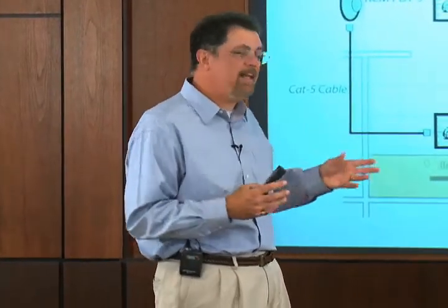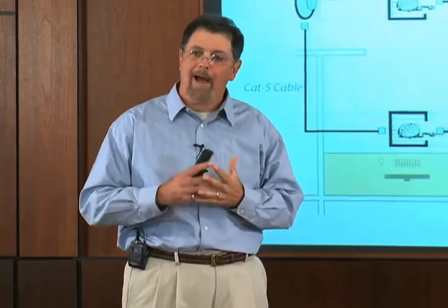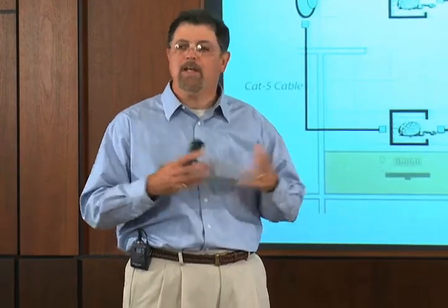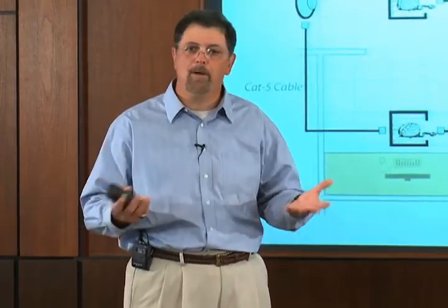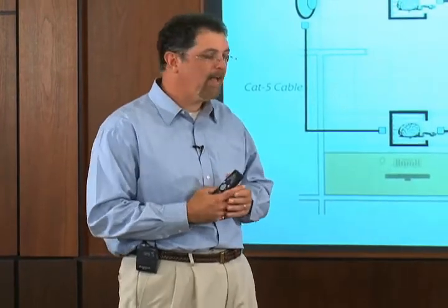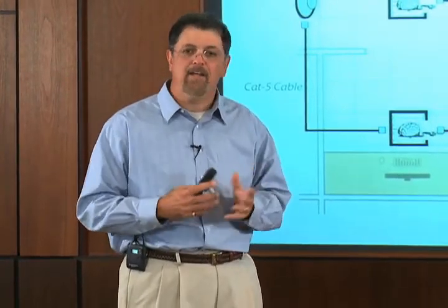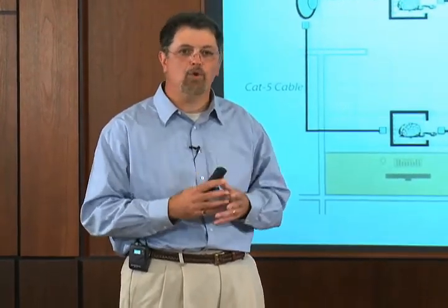The beauty of this is that the control devices are very low power, and they are actually powered by the network itself. So you do not need to run additional auxiliary power to the control devices, and that is key to give this system true plug-and-play connectivity and capability.